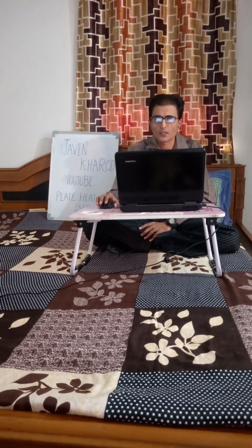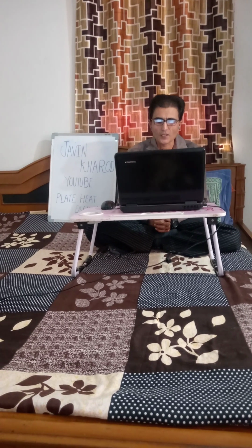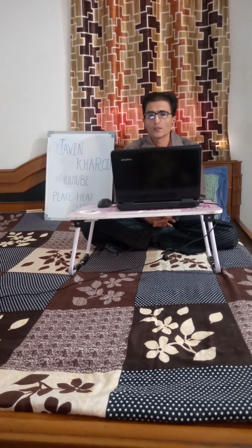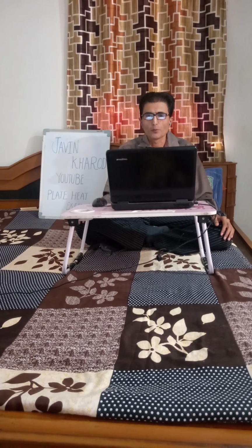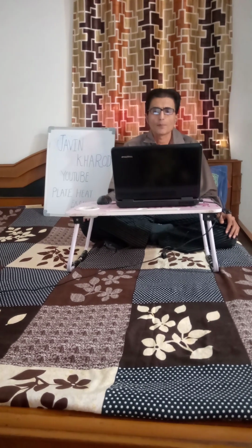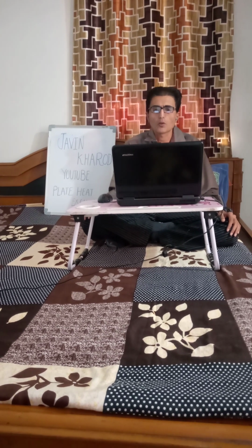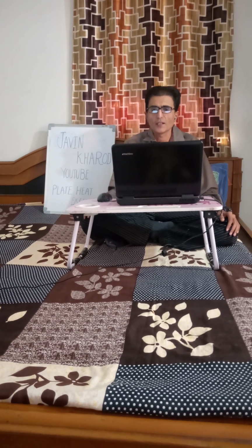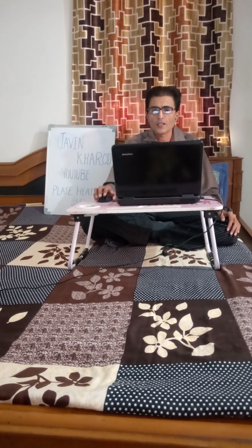by corrugated metal plates. The plates used in a plate and frame heat exchanger are obtained by one-piece pressing of metal plates. Stainless steel is a commonly used metal for plates because of its ability to withstand high temperatures, its strength and its corrosion resistance. The plates are often spaced by rubber sealing gaskets which are cemented into a section around the edge of the plate.